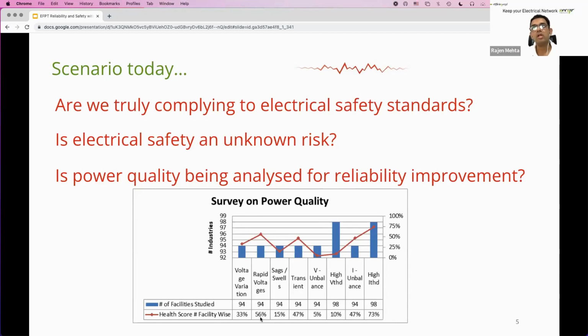56% of facilities experienced rapid voltage changes, similar to a voltage dip or very fast change in voltage. 47% experienced fast-acting transients, on the order of a few microseconds to nanoseconds. 47% had high current imbalance, one of the reasons for increasing neutral currents and circulating currents. And current harmonics exceeded limits set by IEEE 519 or CEA standards in 70% of facilities.